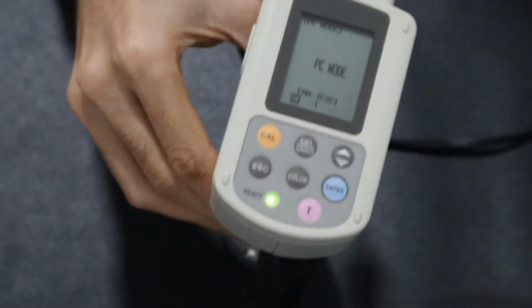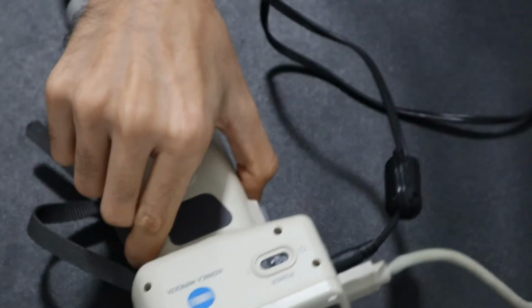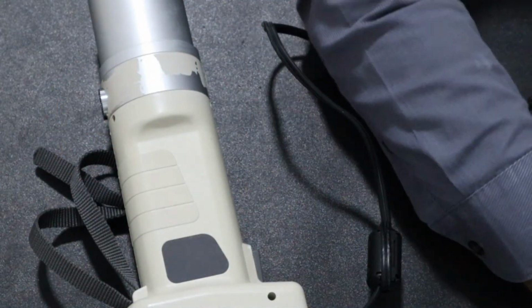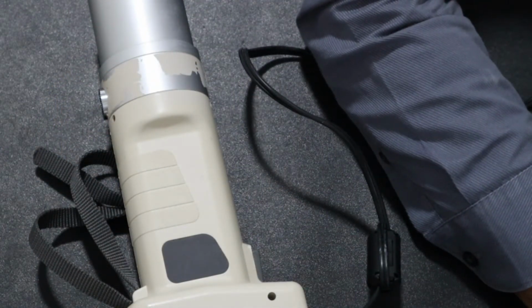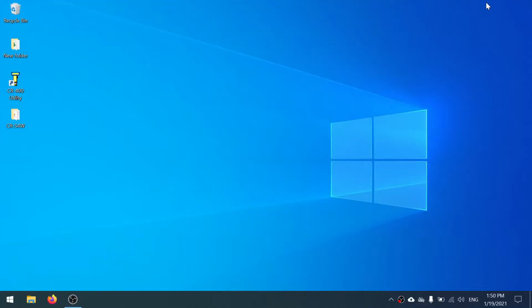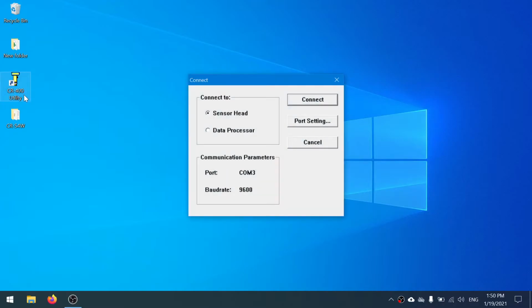So the next thing we need to do is turn on the software and get it communicated. So I will show you my view on the PC. Sorry. So on the PC, once you've installed the utility software, we have to go ahead and run it with this CR-400 utility. Here we have an option between sensor head and data processor. So we'll select sensor head, and before we click connect, I would recommend you to go to port setting, since the communication parameters is set to COM3.